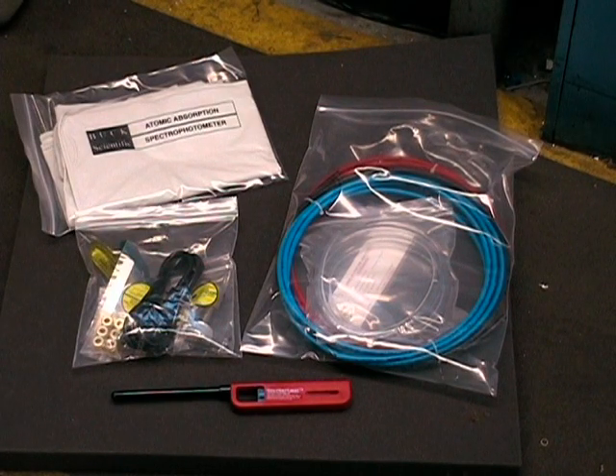The basic installation kit will include a dust cover for the instrument, a bag with a series of 1/4-inch Swagelok fittings, a series of hex wrenches for removing the burner head and drain block, power cable, and some nylon tubing for the gas lines and Tygon tubing for the drain line. Ignition of the flame is accomplished with a barbecue lighter enclosed with the installation kit.